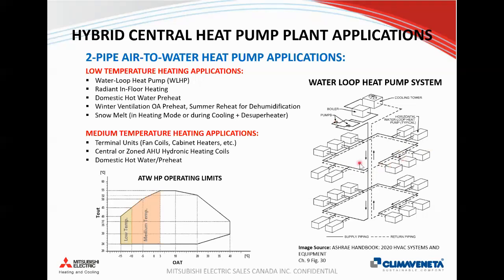So this is a really good application for air-to-water heat pumps because it lets you use it all the way down to -15 and cover off a significant majority of the hours throughout the year. But also, you don't even need to supply 35 degrees in these systems. You can supply 30 degrees, maybe even lower. So the lower the temperature, the more efficient the machine will run as well. So that's something to leverage as part of the design process.